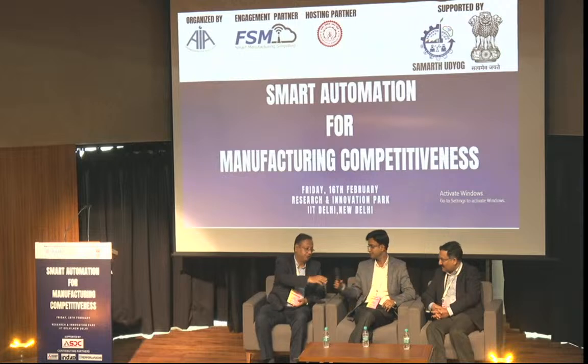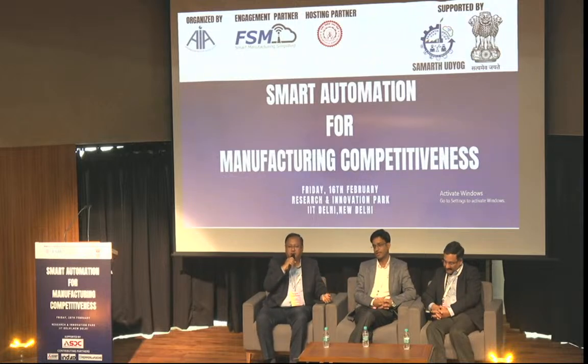Thank you, sir. I would just like to add one more line. We have a product directly usable for vibration monitoring. It uses FFT, as most equipment manufacturers use FFT for analysis. The beauty here is you have a ready-made program given to you on the HMI, and it takes 2 or 3 days to commission it. So what it means is you have a pre-tailored GUI made available by Mitsubishi, tested by Mitsubishi, and you can connect sensors like IFM sensor or any other standard sensor. The only constraint is you should use acceleration type sensors, not velocity type. The make is not very important.